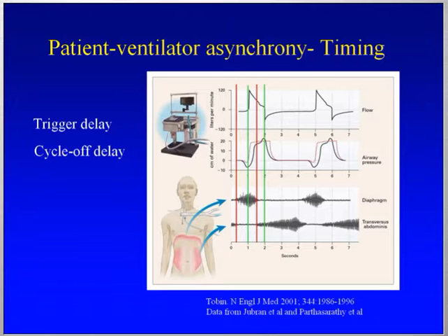But also important, like Art pointed out, there's actually a delay between when the EMG signal stops and the ventilator continuing to deliver assist. So when you compare the patient's neural inspiration with the ventilator-delivered timings, you can see that the overlap period is very short.